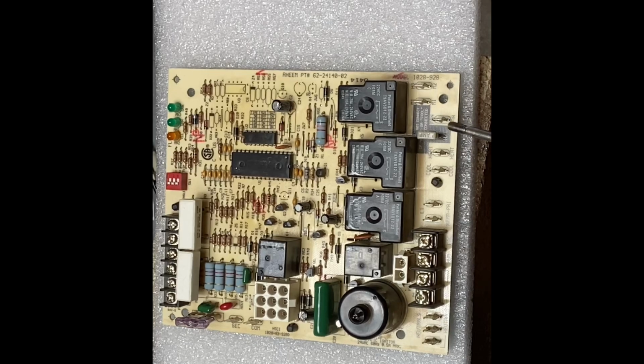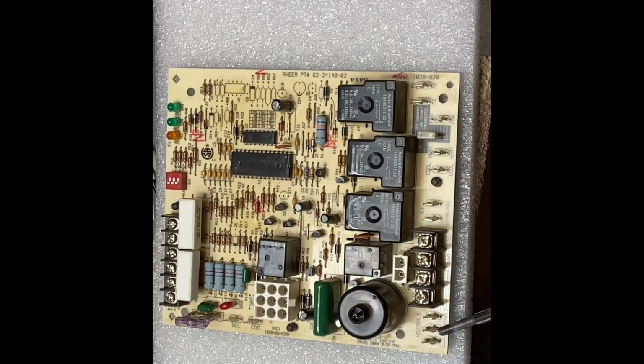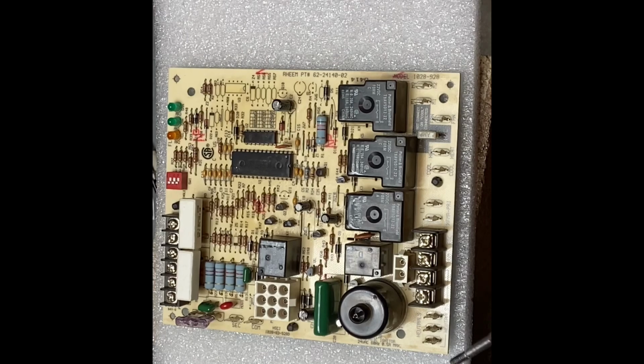We have another relay over here for fan. This is going to be continuous fan. If we leave the fan on position, we can set whatever speed we want to keep the air circulating. It's only going to use one of these speeds at a time, and no matter what speed we use, it's all going to come back through 1 wire on the neutral.